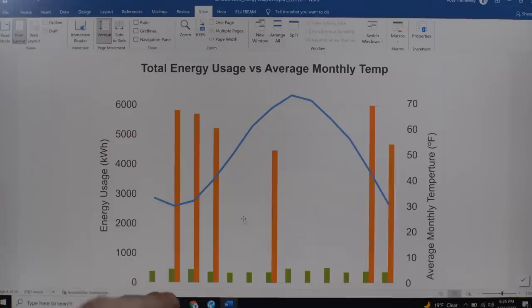The other thing to point out is the heating. This represents how much energy you're using for oil — the orange — and how much you're using for electricity in the green, from January to December. You can see you're obviously using more oil in the winter months — it's expensive. One thing you could do is go to a natural gas option, but there is no natural gas in the street. The next best approach would be an air source heat pump — mini splits, multi splits, ducted or ductless. That type of system is going to save about $500 or more a year, and the side benefit is that they provide some cooling and dehumidification.